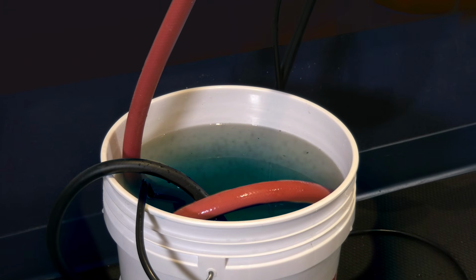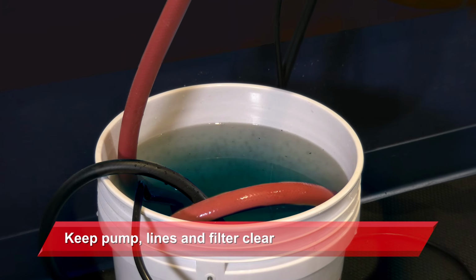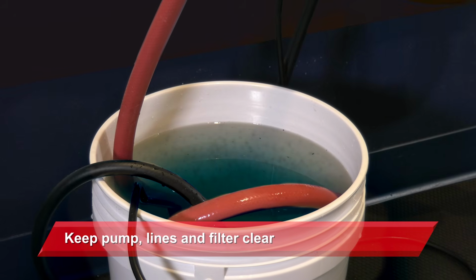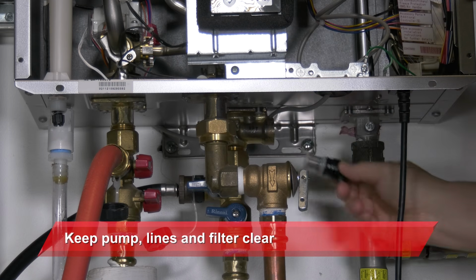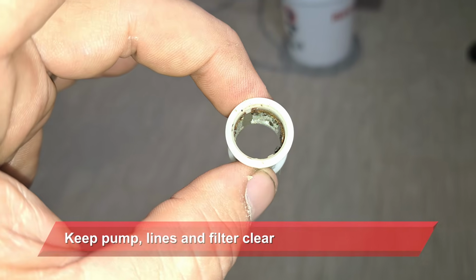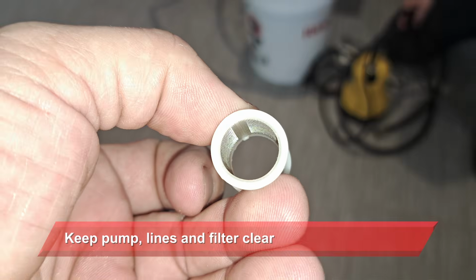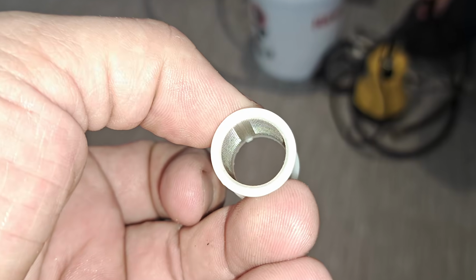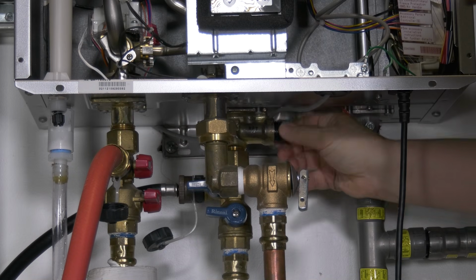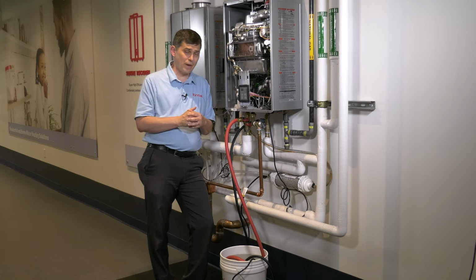If there is a good bit of scale coming into the bucket, ensure your pump and lines remain clear. You may want to stop the flush at 30 minutes, quickly check the inlet filter, and then finish the flush. But remember, keep that filter in the water heater while flushing. So during this 1-hour flush, here are some other simple maintenance checks that can be performed.